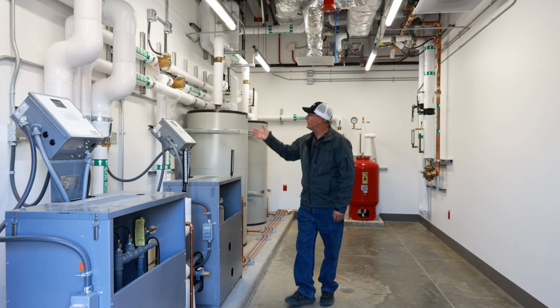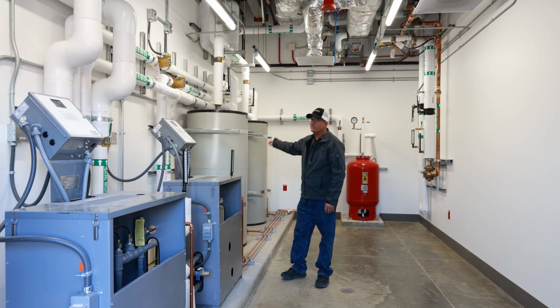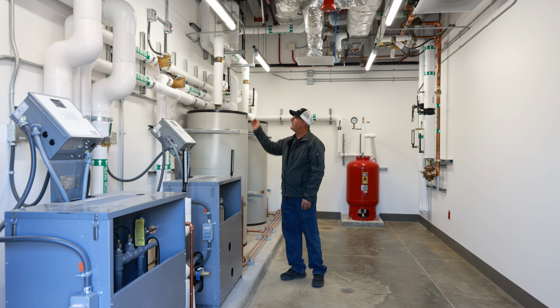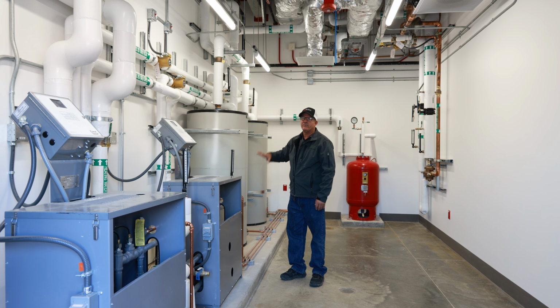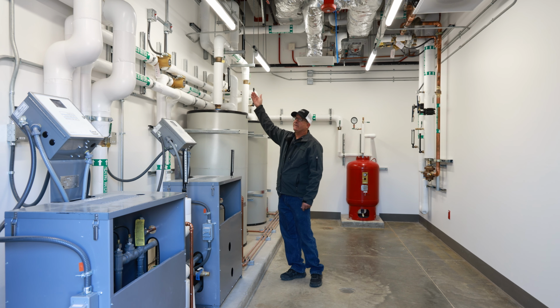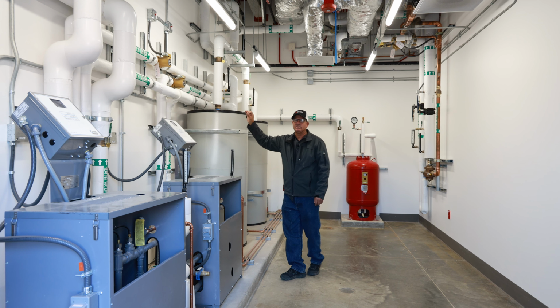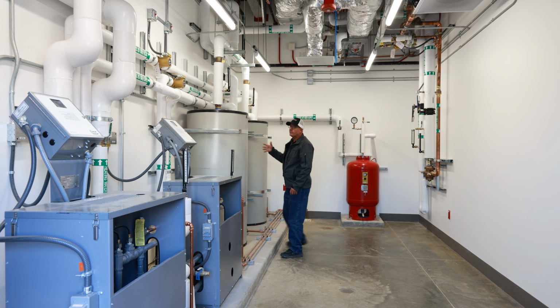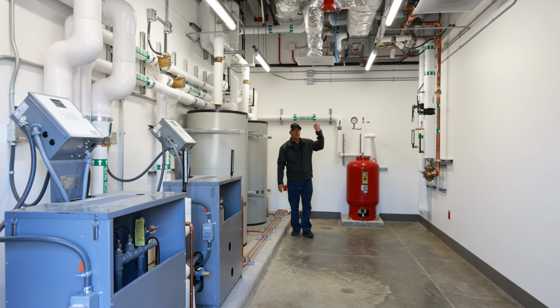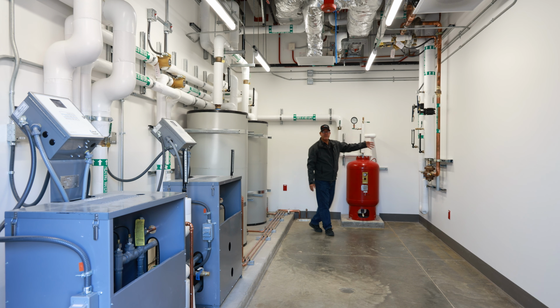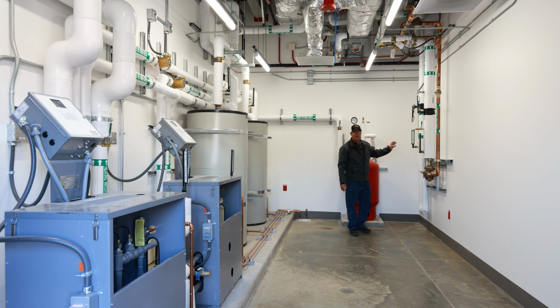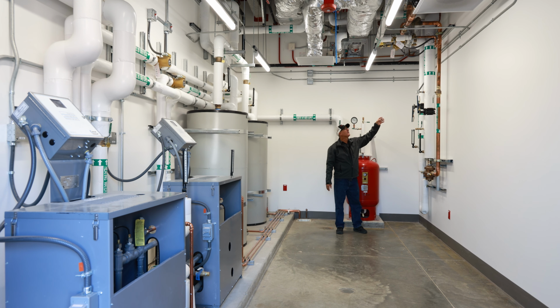Out of the heat exchangers, we move over to our storage tanks, our domestic hot water side. These are our two circ pumps circulating from the tanks through the heat exchangers. The disconnects are located right above them. There are speed switches on the side. No need to adjust them. They've been balanced. Out of our storage tanks, our domestic hot water goes over to our mixing valve. It is tempering the water to 120 degrees and out into the building.